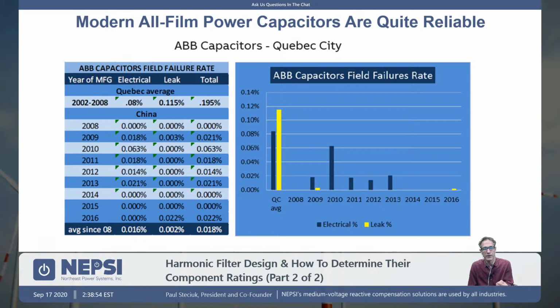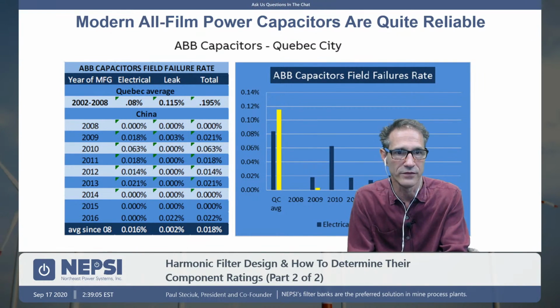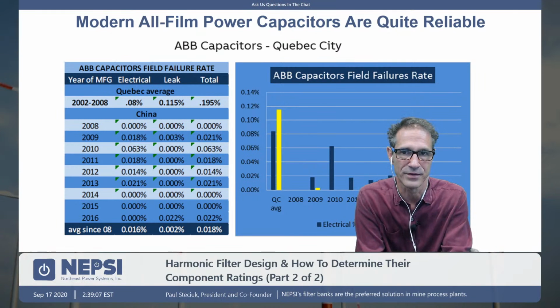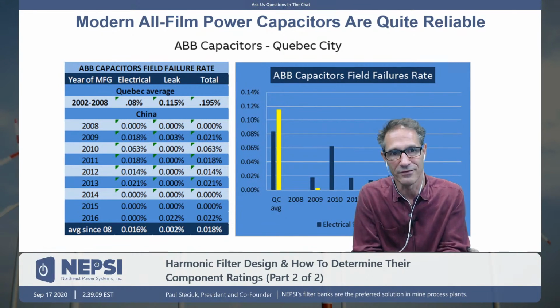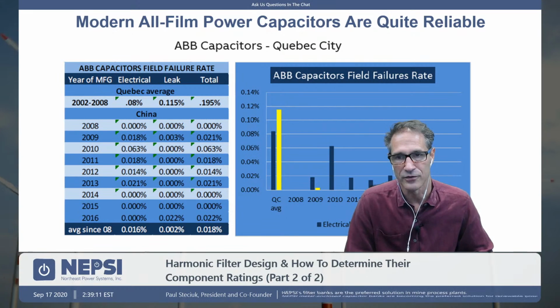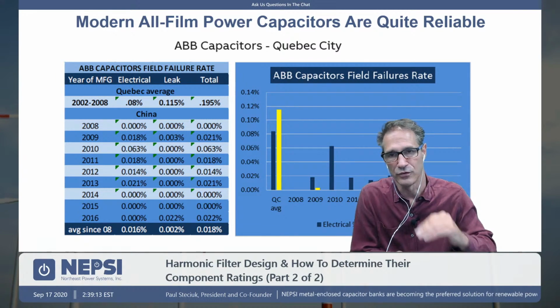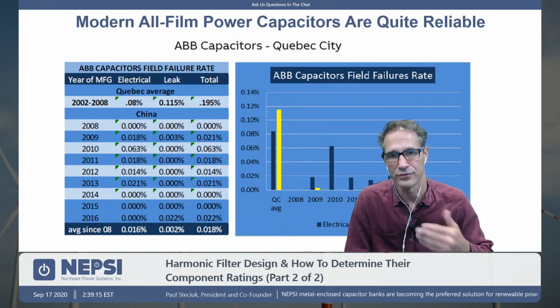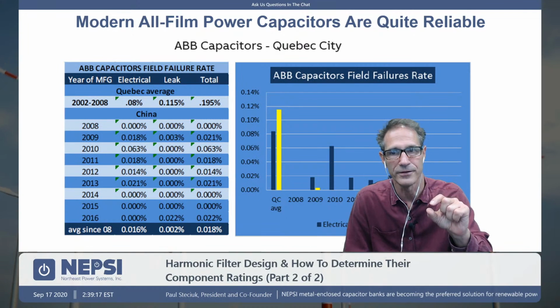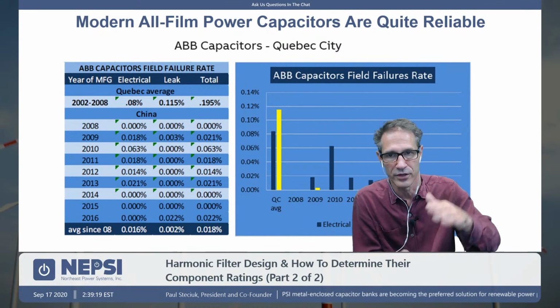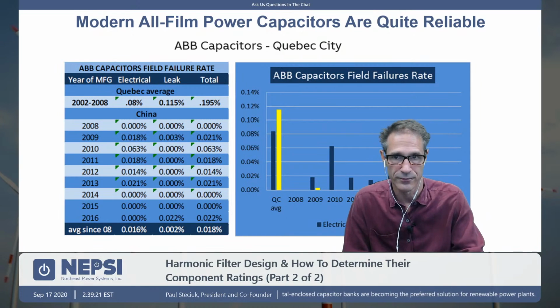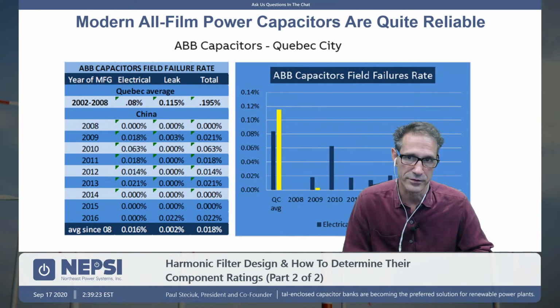So if you think about, well, go with a conservative design. Say the system requires 9.54 kV. Instead of going 9.54 kV, go with 9.96 kV. And your failure rates will be even less than 1 in 5,000. So always think about adding some voltage to the capacitor. It's going to bump up the price a little bit, but it's going to even increase the reliability further. And in critical process plants, reliability is important.